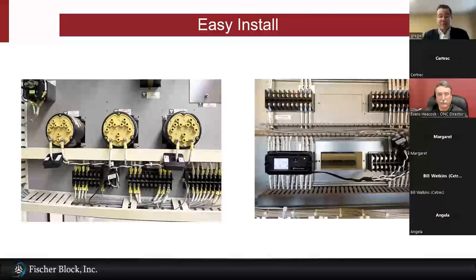Sometimes, if there's access to the back of the panel - some of the panels in substations on the grid and within plants, you can walk to the back as easy as the front - we can install our device right to the back of the panel. In this case, it's to the back of a flexi style test switch. We have ruggedized push pins underneath picking up three-phase voltage, and then again we'll snap on a three-phase split core CT assembly right there next to our device.